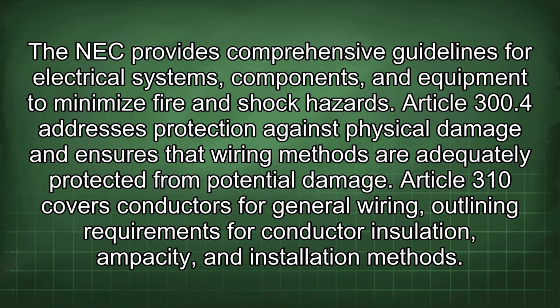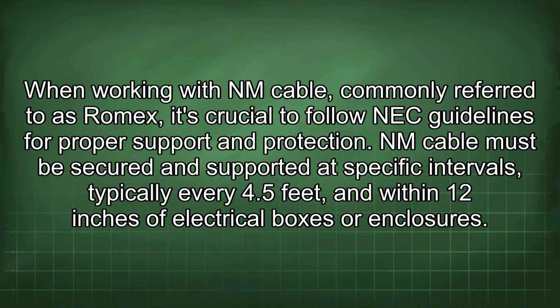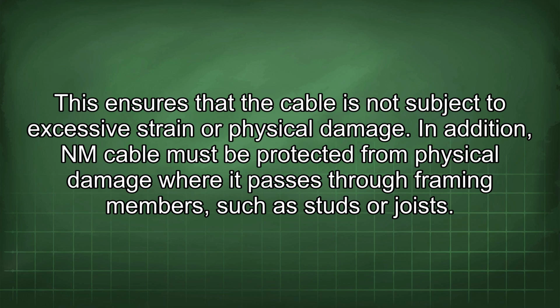Article 310 covers conductors for general wiring, outlining requirements for conductor insulation, ampacity, and installation methods. When working with NM cable, commonly referred to as Romex, it's crucial to follow NEC guidelines for proper support and protection. NM cable must be secured and supported at specific intervals, typically every 4.5 feet, and within 12 inches of electrical boxes or enclosures. This ensures that the cable is not subject to excessive strain or physical damage.